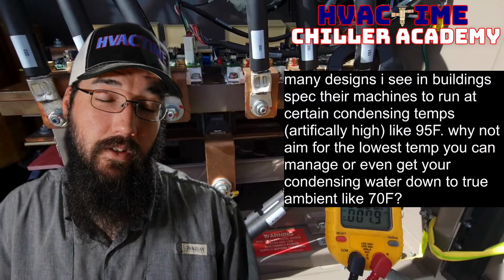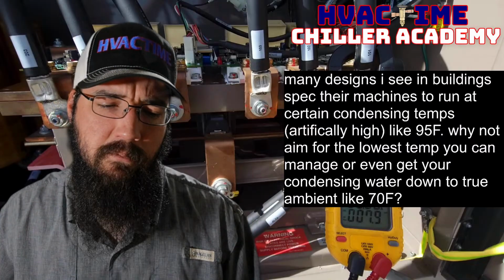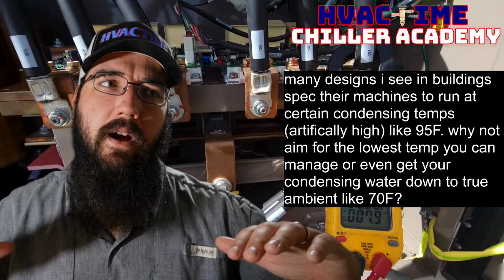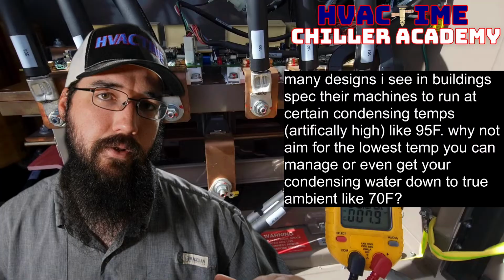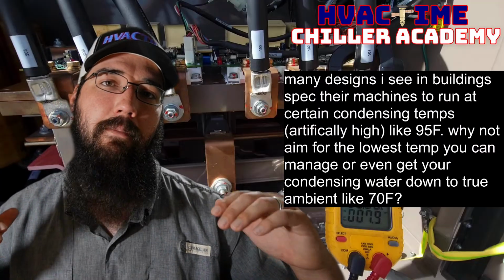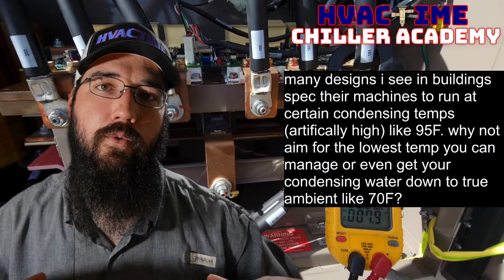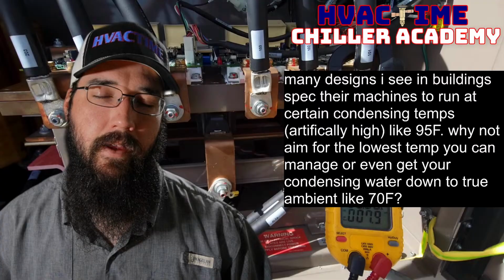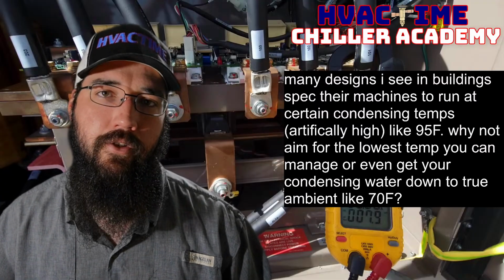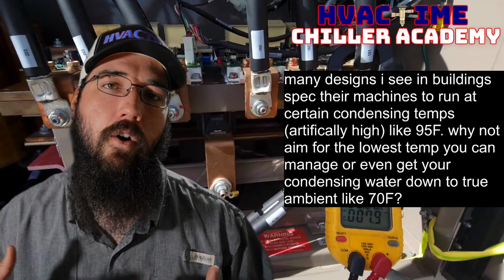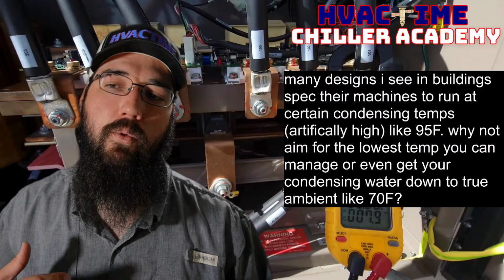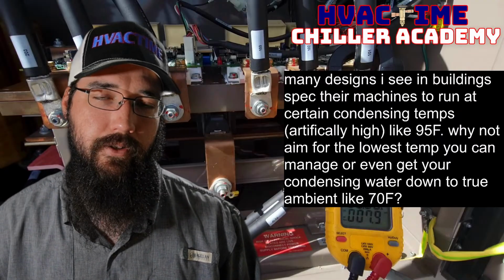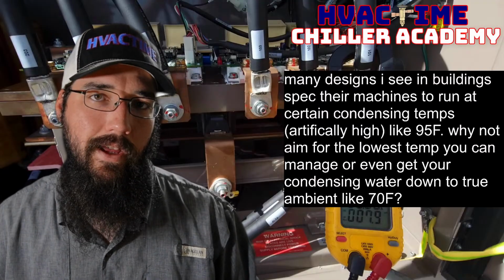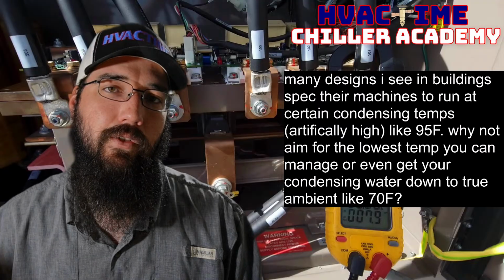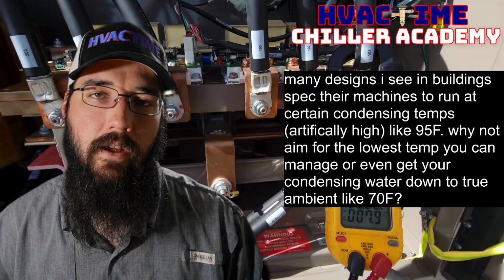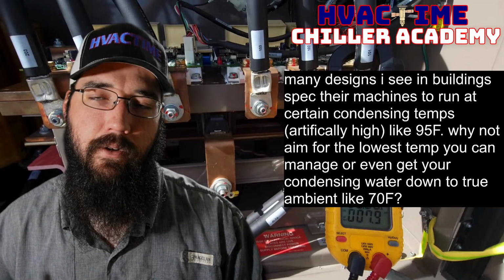Because in most cases, unless we're dealing with just really small equipment, a couple of degrees or several degrees of temperature change on the condenser water can mean significant load reduction on the compressor, because its amount of energy is directly correlated to how hard it's having to compress. So the higher we force our condenser pressure, the harder the compressor has to work in order to achieve the condenser saturation that we need in order to allow for the proper heat transfer process.